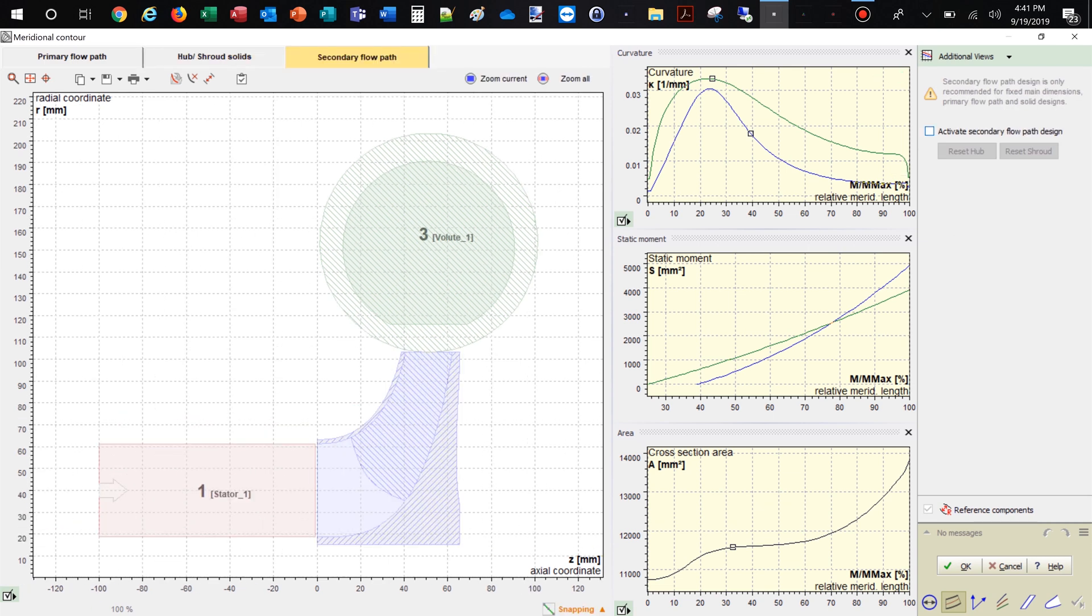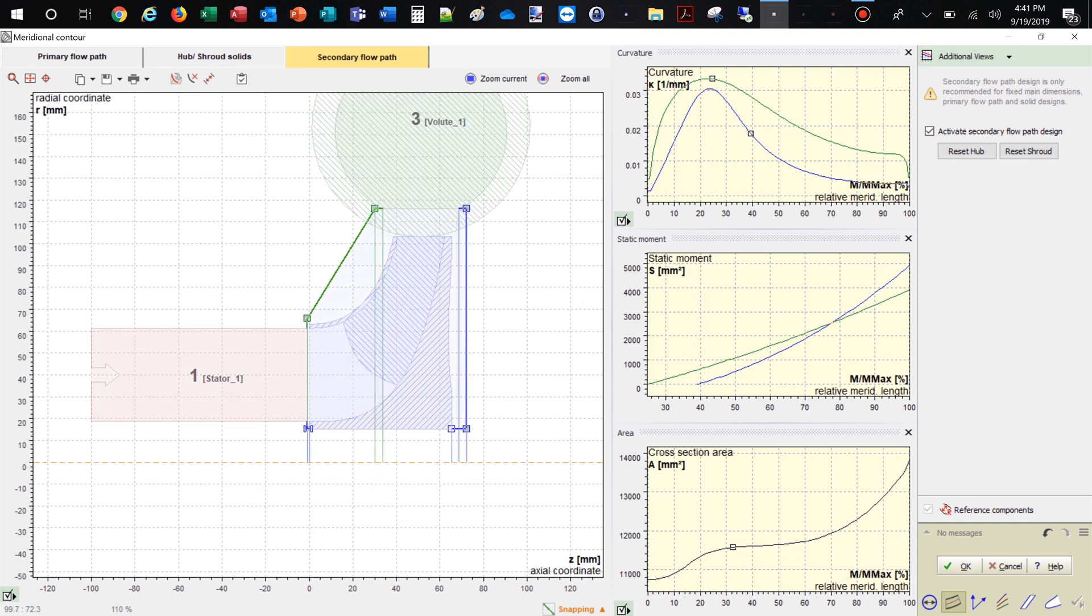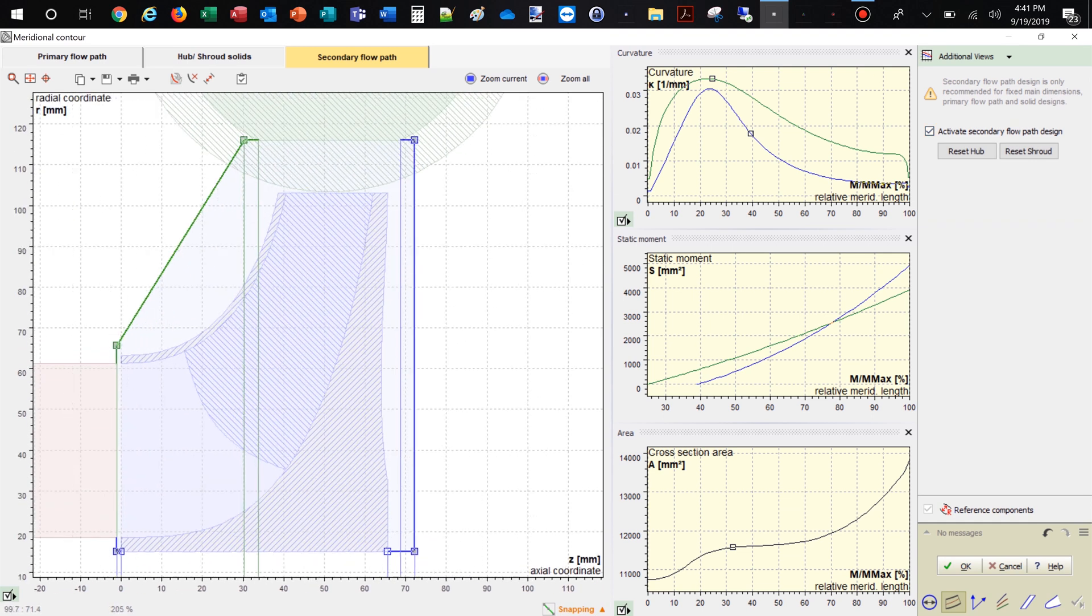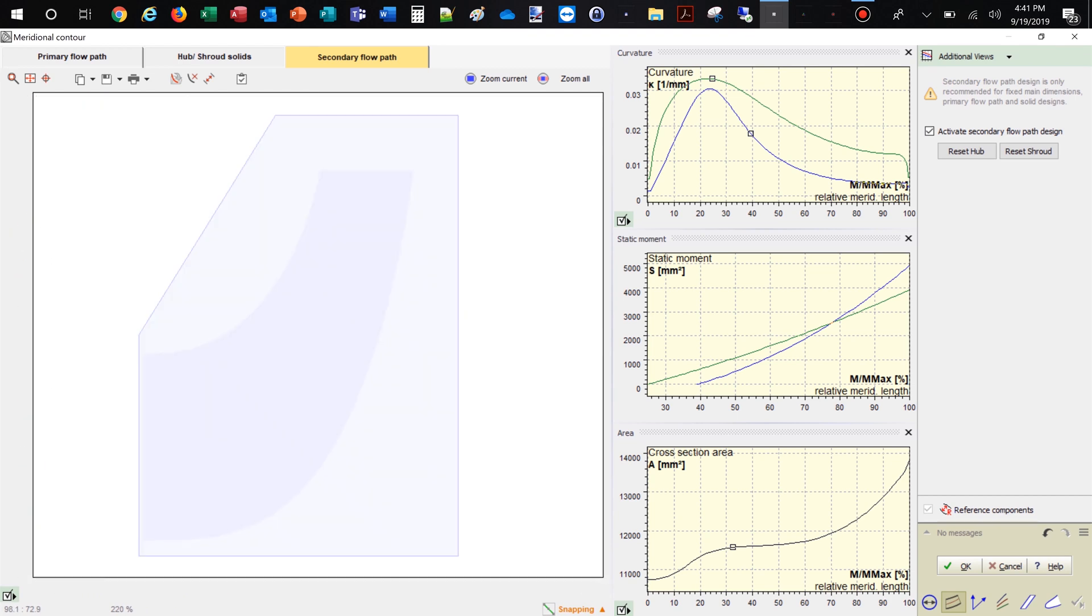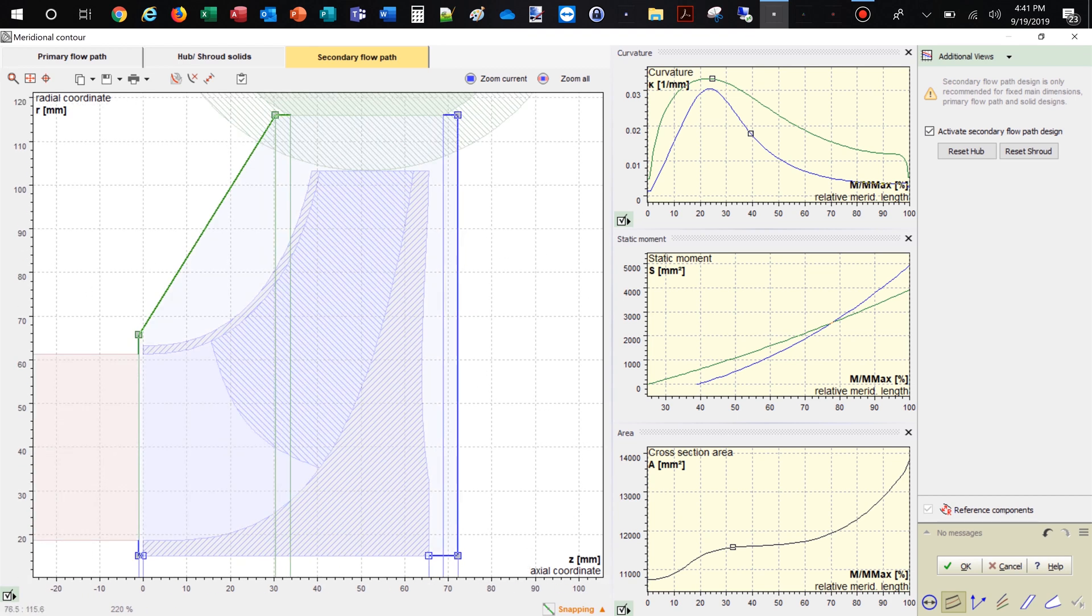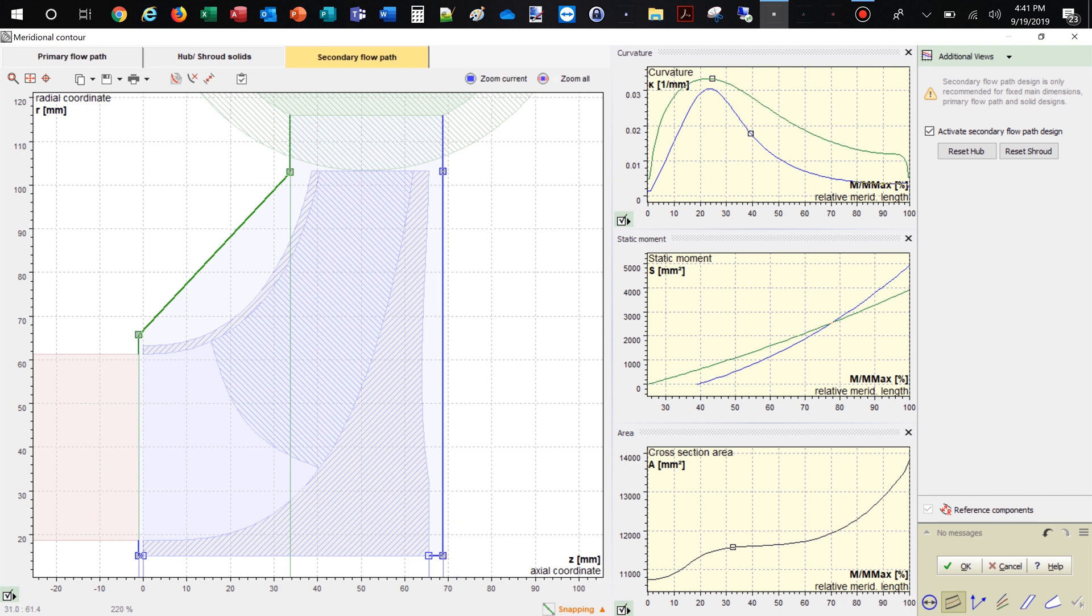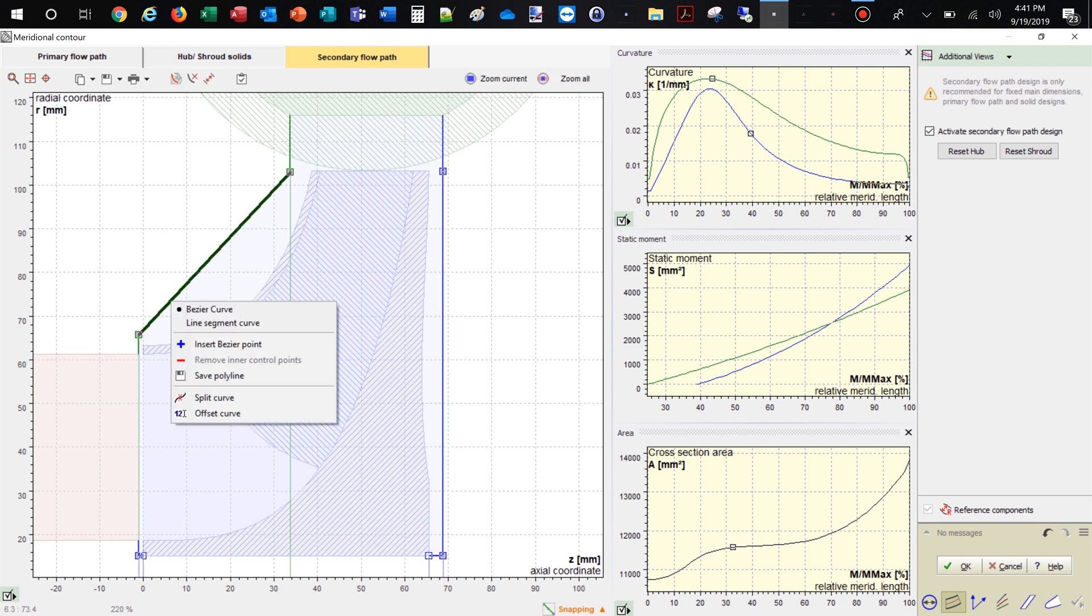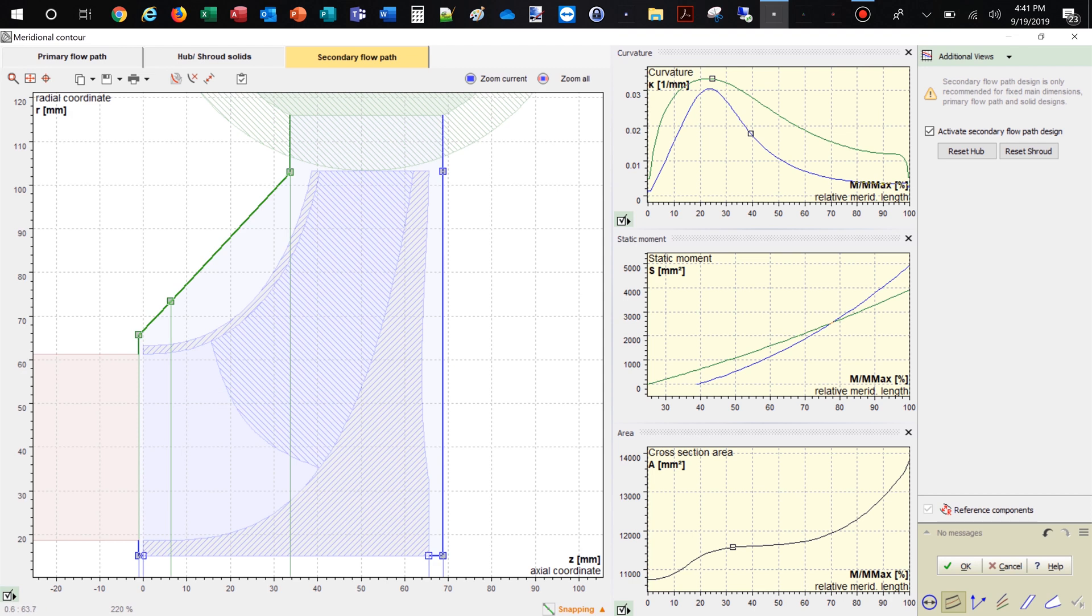The initial secondary flow path describes a simplified space which can be adjusted by drag and drop of Bezier points. The corner points can be adjusted graphically or numerically. The lines can be transformed into Bezier splines. For example, we modify the casing contour near the eye of the impeller. This is very often used to design a small gap to minimize volumetric losses.